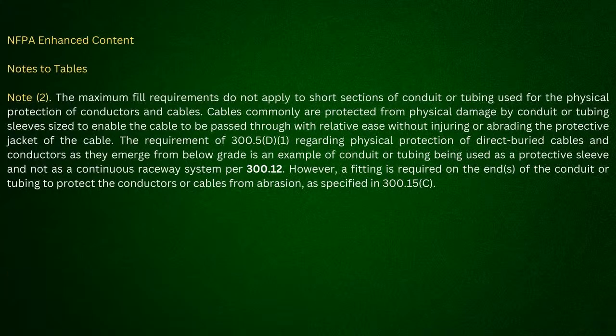But, you know, just to wrap this up, I'm not going to argue with him on that. Basically, I look at Chapter 9, Table 1, Note 2. You've got to be complete on both ends. If it's 24 inches or less, it's a nipple. It specifically states that in Note 4. And then if I go look at 310.15C1, it says in order to apply the adjustment and correction factors, it has to be a raceway. And therefore, a sleeve is not a raceway.